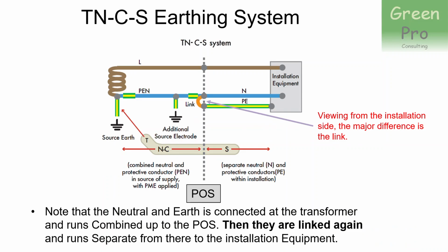So on a TNCS system, you also connect the neutral to the earth at the transformer, and then you run a single conductor to your point of supply. By point of supply, I mean the box in the street where your meters are. Now the big difference is if you view this from your installation side, in other words, from your main DB, then there is a link at the point of supply, call it at your meters. There is a link between the neutral and the earth. And from there on forward, you have a separate neutral and a protected earth. That's really the only difference.